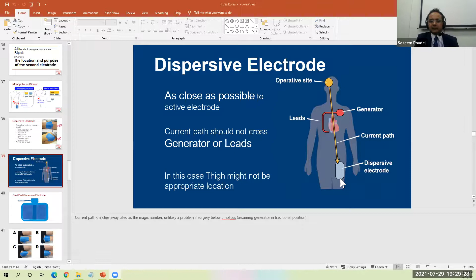This is regarding what to do when there's a pacemaker. The electricity always travels from the operating site active electrode to the dispersive electrode. So if there is a pacemaker, one way to avoid issues is to place the dispersive electrode as close as possible to the active electrode and not crossing the generator. If you put the dispersive electrode on, say, the right arm, it can go this way, not crossing, which will lead to smaller damage. If it's the abdomen side, the dispersive electrode inside can be an answer.